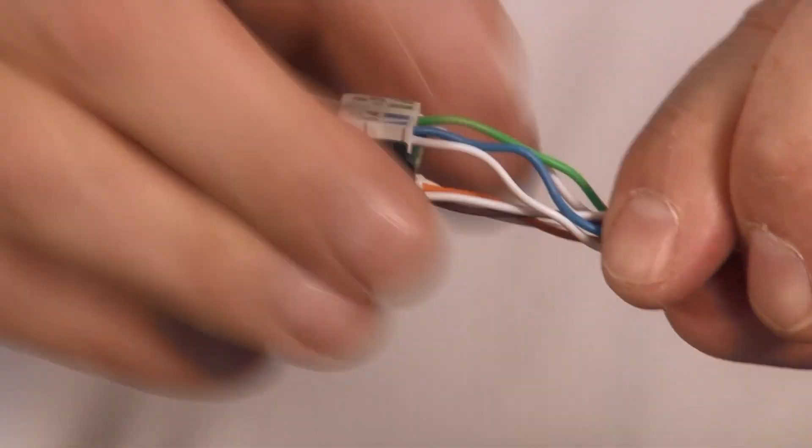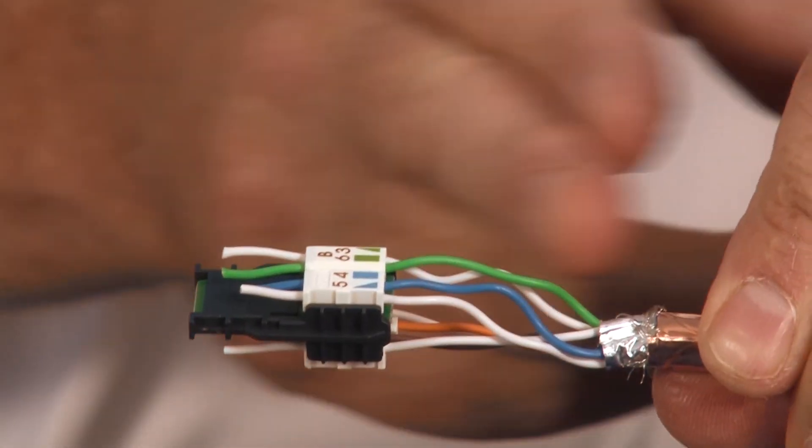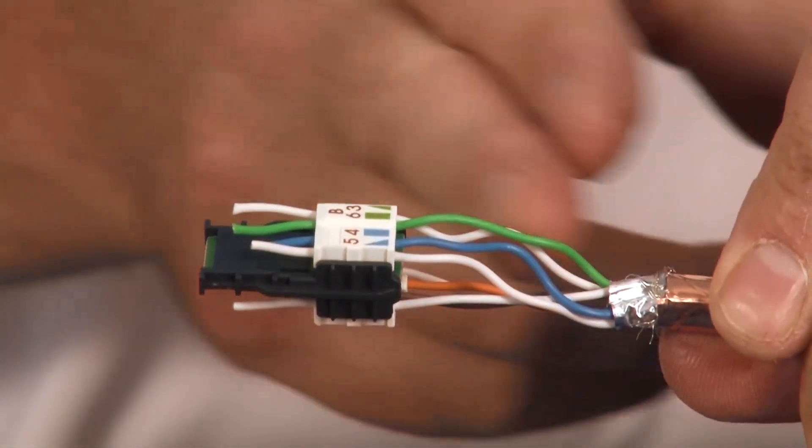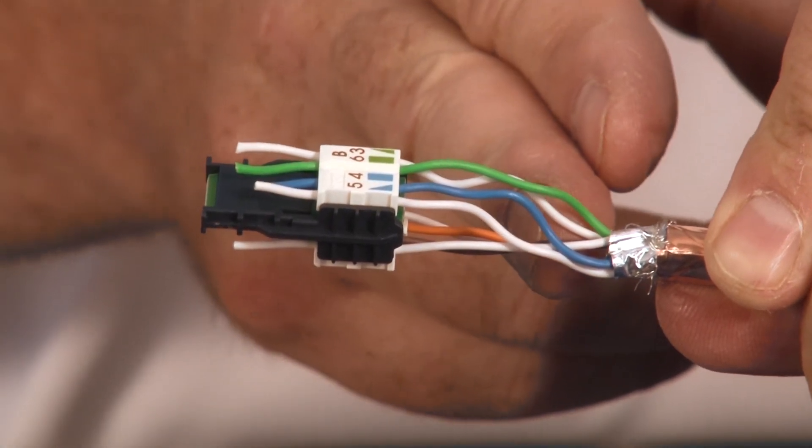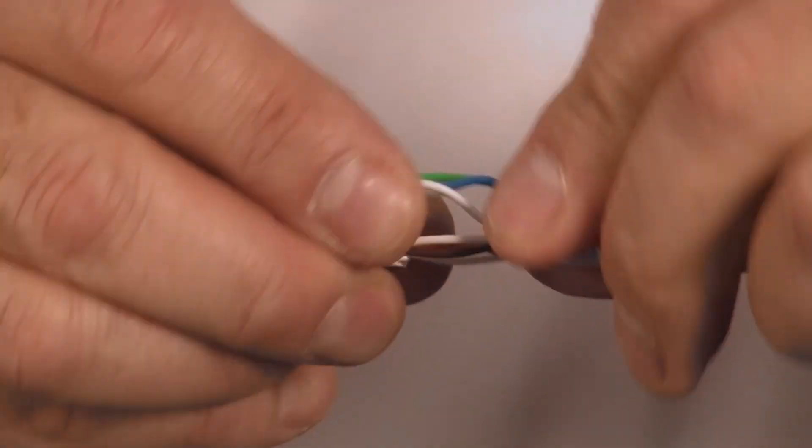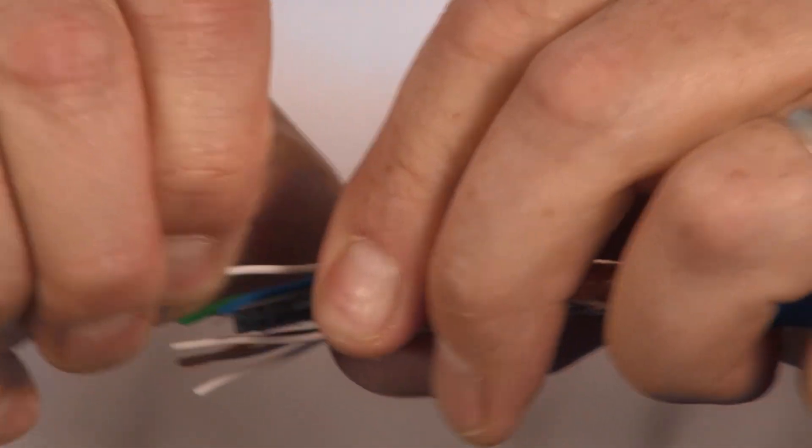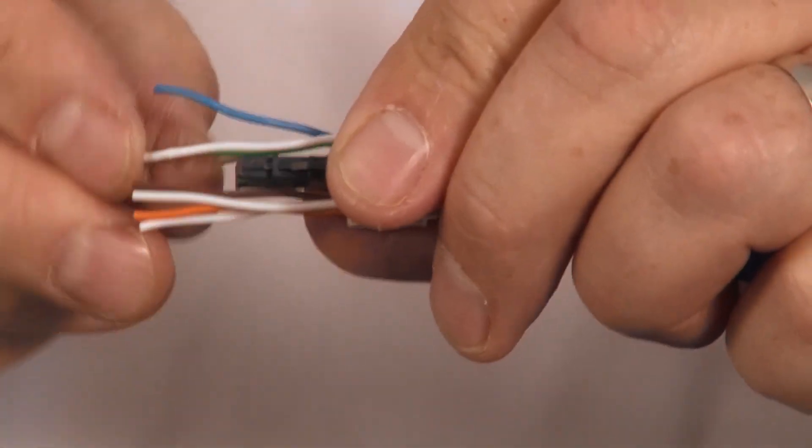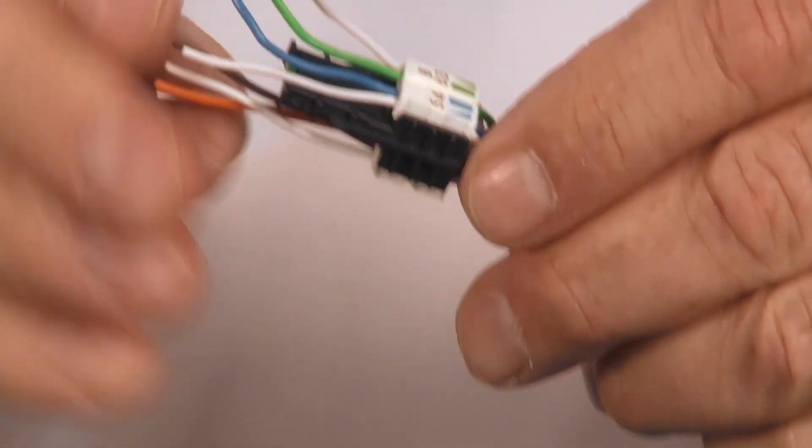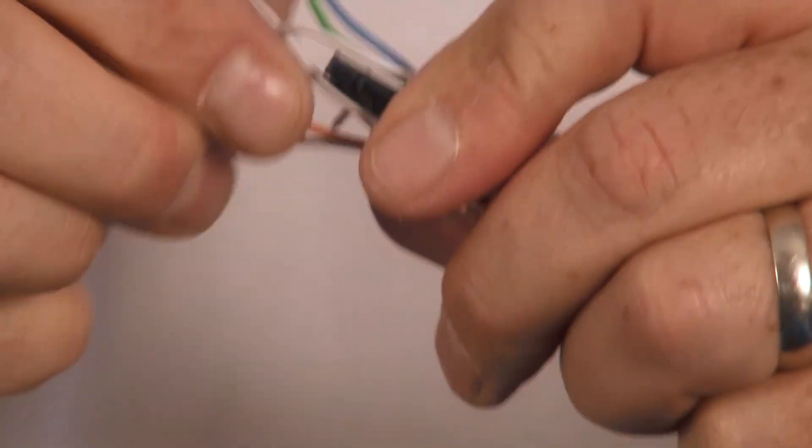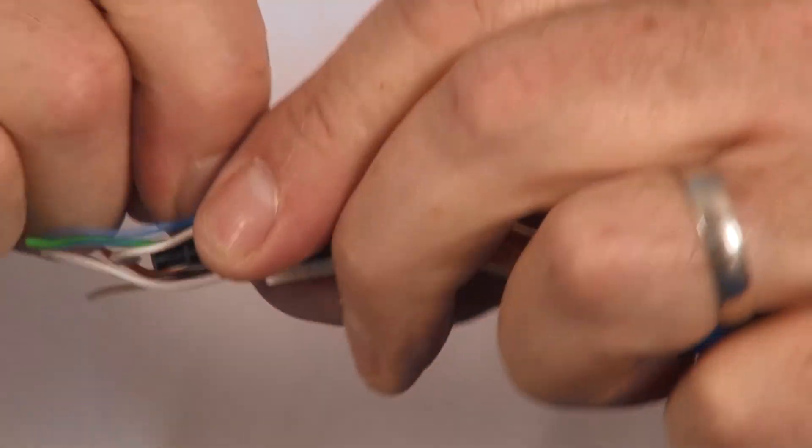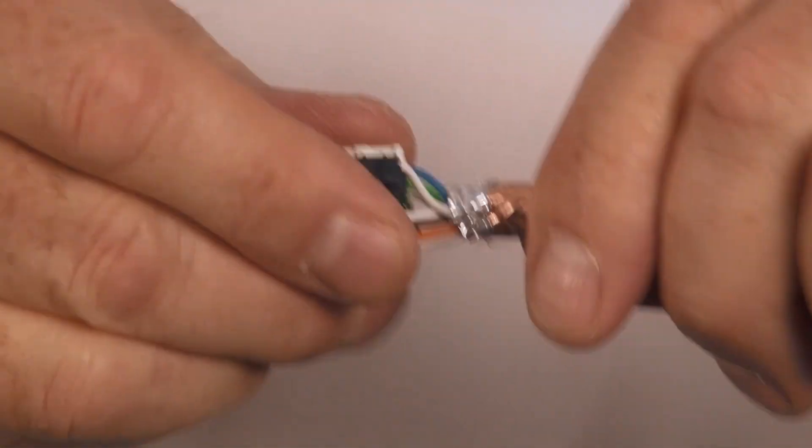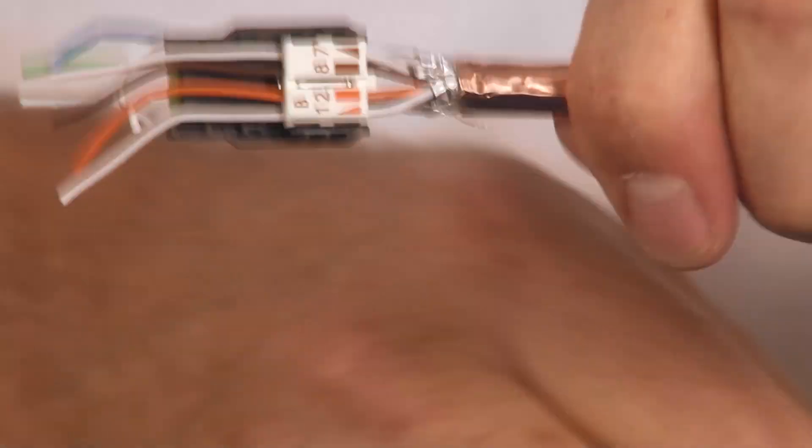Once I get them all inserted, now I want to slide them up the cable as far as I can. You want to follow the TIA instructions as far as untwisted pairs. You only want to have about less than a half of an inch or less is better. You go ahead and seat this down. Sometimes you have to help the conductors. Give it a little pull. These are very large conductors with the insulation they have on them. Just get them down as close as possible.